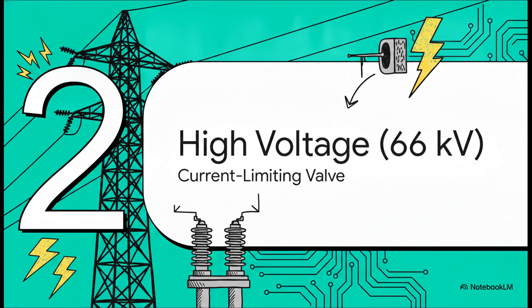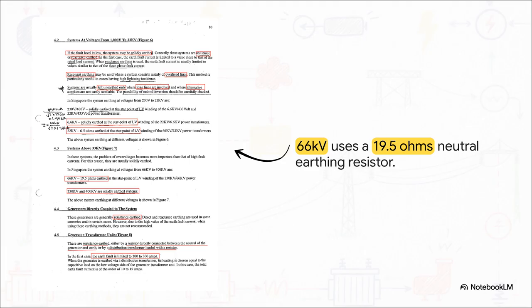Moving on to Tier 2, high voltage at 66 kilovolts, the current-limiting valve. Okay, so here's the catch. We can't just leave those floodgates wide open at 66 kilovolts. It doesn't work. To deliberately cap that fault current, the 66 kilovolt system is grounded through a very specific piece of equipment. We use a 19.5 ohm neutral earthing resistor, or NER.